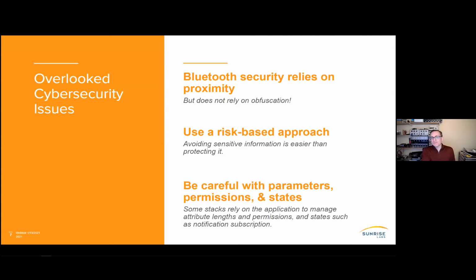And so the goal is to try and move it as far to the easy end of that spectrum rather than the hard end of that spectrum. And it's usually easier than it sounds. It's rarely the case that your Bluetooth peripheral, which is usually the medical device, needs to have identifiable information about the patient, right? Usually that can be stored on the person's phone. They can enter it themselves in the phone. That's not really part of your system, so you have less control over the security of it, and you rely on the person's judgment to control that information.